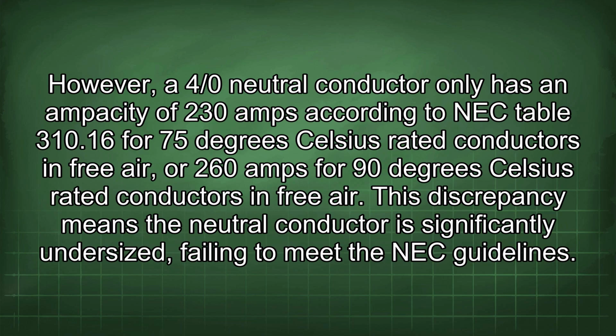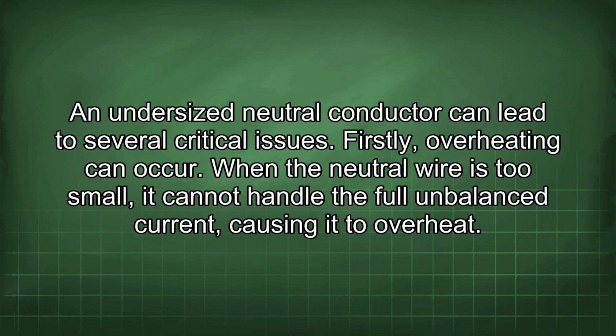However, a 4/0 neutral conductor only has an ampacity of 230 amps according to NEC Table 310.16 for 75 degrees Celsius rated conductors in free air, or 260 amps for 90 degrees Celsius rated conductors in free air. This discrepancy means the neutral conductor is significantly undersized, failing to meet the NEC guidelines. An undersized neutral conductor can lead to several critical issues.